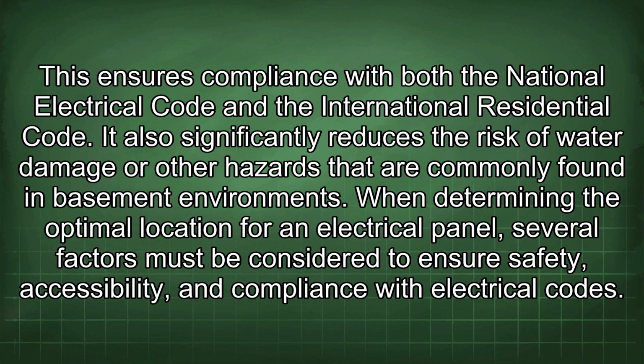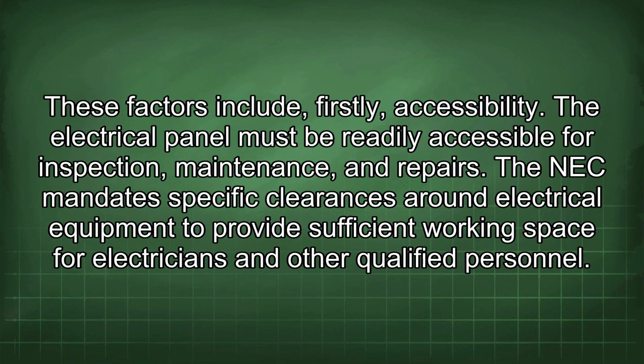When determining the optimal location for an electrical panel, several factors must be considered to ensure safety, accessibility, and compliance with electrical codes. These factors include, firstly, accessibility. The electrical panel must be readily accessible for inspection, maintenance, and repairs. The NEC mandates specific clearances around electrical equipment to provide sufficient working space for electricians and other qualified personnel.